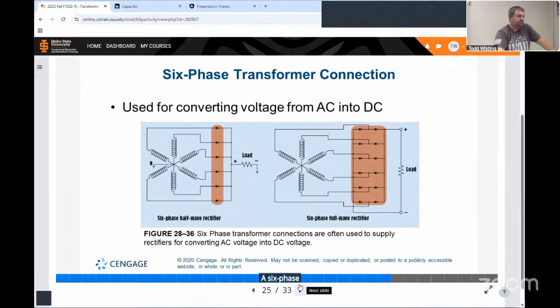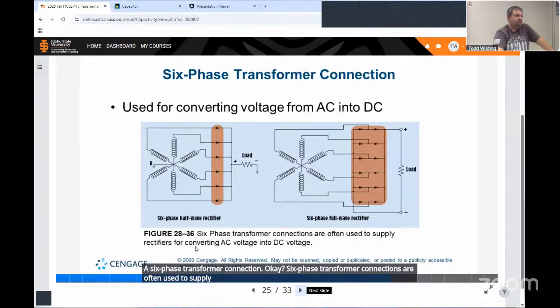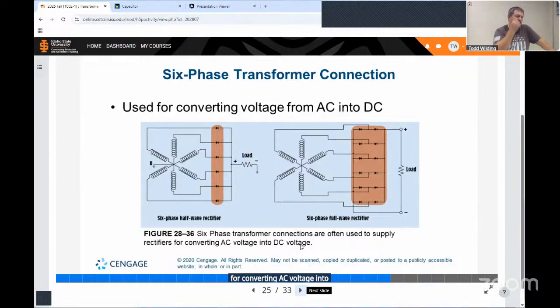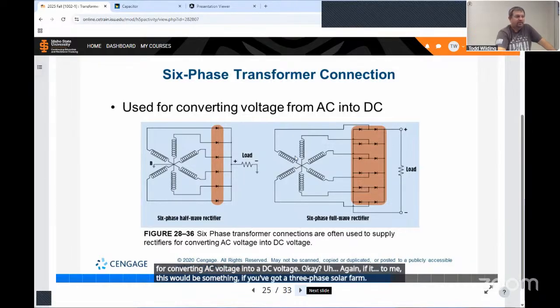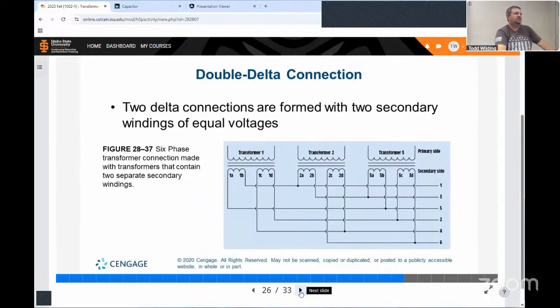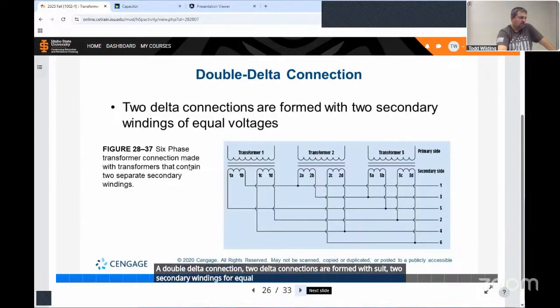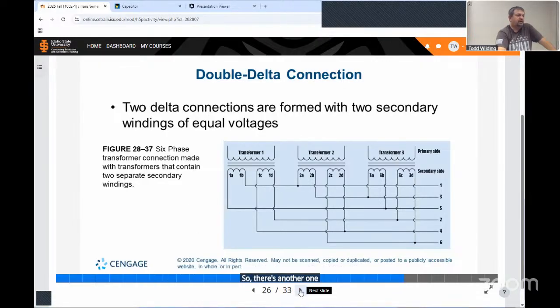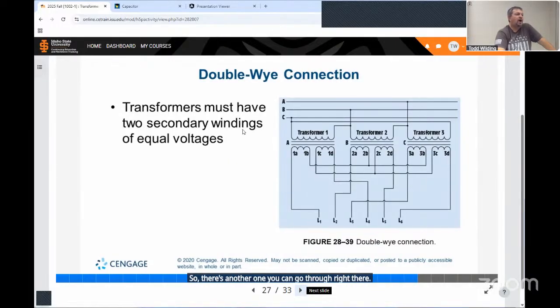6-phase transformer connection. Okay. 6-phase transformer connections are often used to supply rectifiers for converting AC voltage into DC voltage. Again, to me, this would be something that might come into play if you've got a 3-phase solar farm, but I have not seen those either. A double delta connection: 2 delta connections are formed with 2 secondary windings for equal voltages. So there's another one you can go through right there. A double Y. So you just basically got 2 transformers on each primary transformer, if that makes sense. Okay.